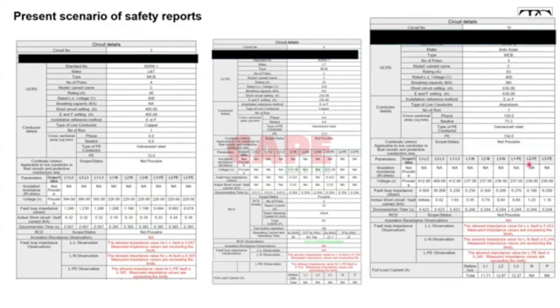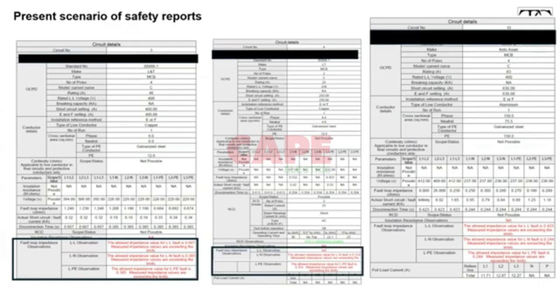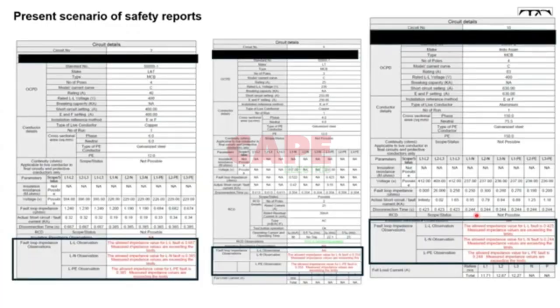So if you see the test reports, the major thing, if you come to the last point, where I have put the black square highlighted part, in most of the areas the fault loop impedance is not actually within limits. It is above the prescribed limits. The allowed limit is 0.423, but the actual loop impedance will be much higher. Due to these reasons, this is one of the reasons why fault loop impedance is not coming out properly.